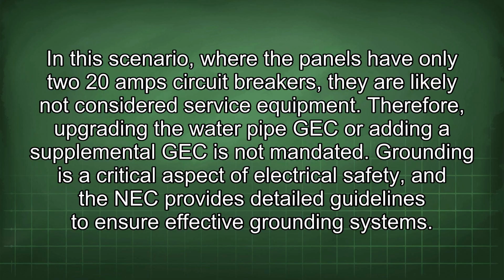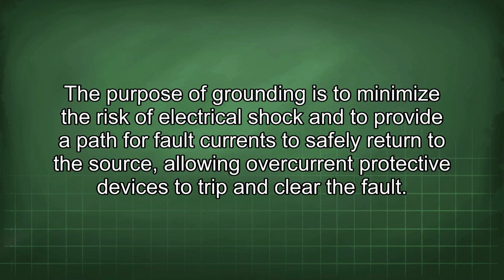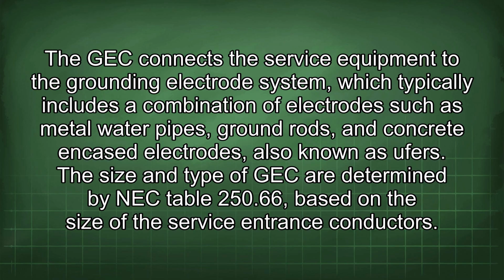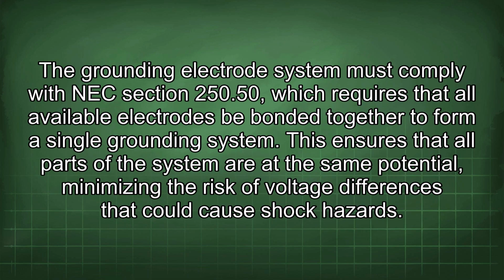Grounding is a critical aspect of electrical safety, and the NEC provides detailed guidelines to ensure effective grounding systems. The purpose of grounding is to minimize the risk of electrical shock and to provide a path for fault currents to safely return to the source, allowing overcurrent protective devices to trip and clear the fault. The GEC connects the service equipment to the grounding electrode system, which typically includes a combination of electrodes such as metal water pipes, ground rods, and concrete encased electrodes, also known as Ufers. The size and type of GEC are determined by NEC Table 250.66 based on the size of the service entrance conductors. The grounding electrode system must comply with NEC Section 250.50, which requires that all available electrodes be bonded together to form a single grounding system.